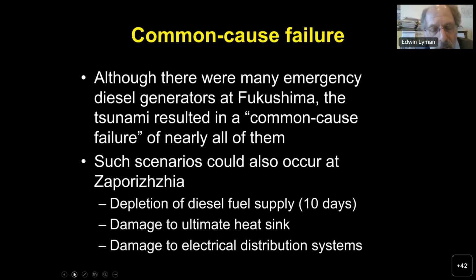But also, you can't expect the backup diesel generators to run continuously and without failure for longer periods of time than that. In fact, they're only rated for 250 hours. So beyond that, you can't expect they're going to continue to operate without being able to maintain them.